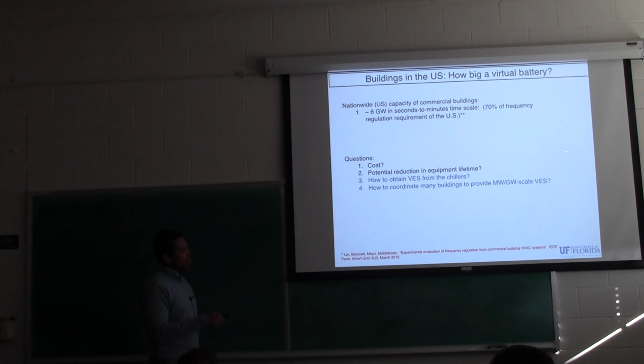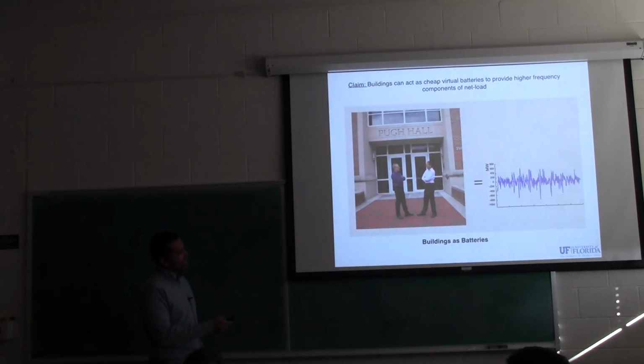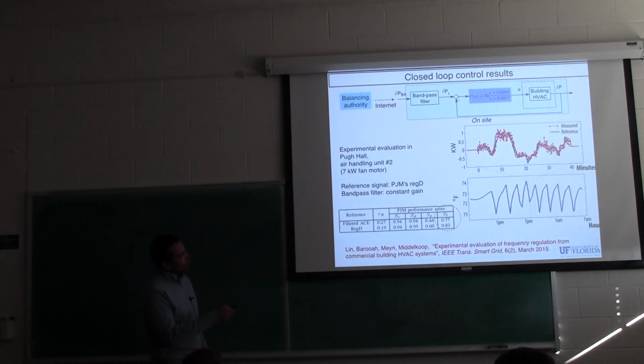The other big research frontier is how do you coordinate many buildings, so every building can do a kilowatt scale. This guy was able to do about a kilowatt up and down, which is quite remarkable because the motor is about 7 kilowatt rated, but normally under baseline conditions it runs at about 2.5 kilowatts. So we do 1 kilowatt variation over 2.5, that's like 40%, and yet no effect in the indoor climate.